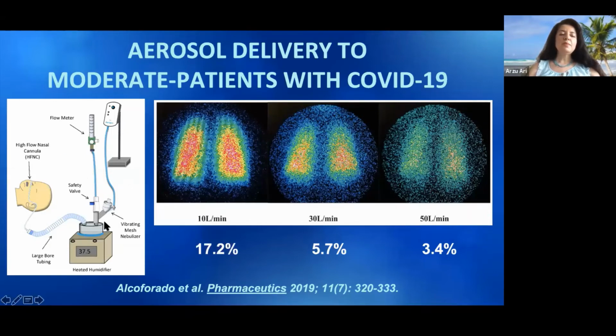So as I mentioned to you earlier, you need to place the vibrating mesh nebulizer here prior to the humidifier. You see this safety valve comes on top of it, and then you attach the flow meter right here, and this is the controller that you are going to use to operate the device. So it's very easy. It's an easy setup. You shouldn't have any problem with it.